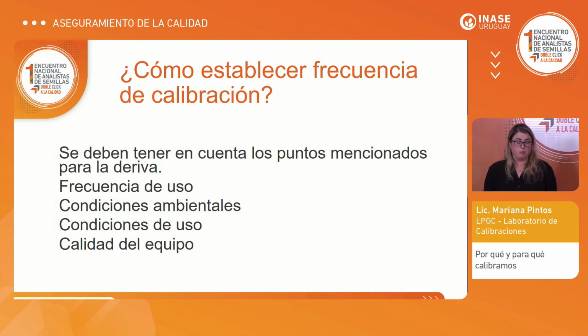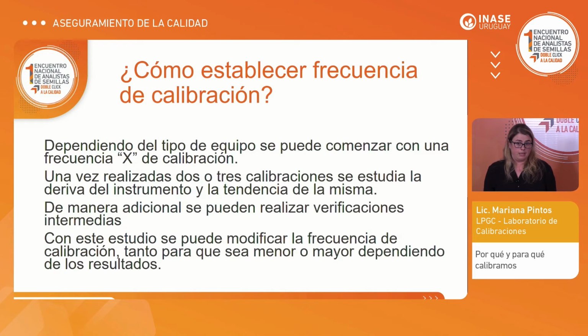How do we set a calibration frequency? We need to take into consideration what affects the drift: frequency of use, environmental conditions, use conditions, and equipment quality. These are very important factors. How can I then set this frequency? Sometimes there is a requirement. Someone tells us that equipment needs to be recalibrated every year, and we do so, and then we can evaluate how the equipment evolves over time.